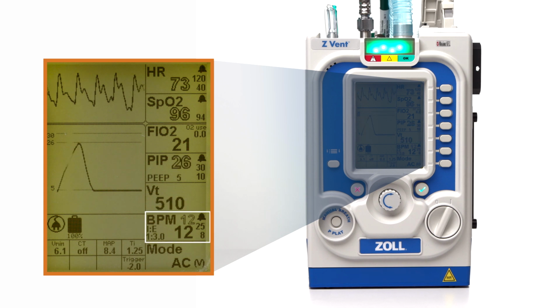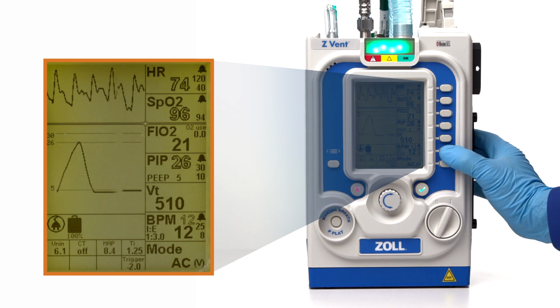The sixth window is breaths per minute, or BPM. In this window, the user can set the desired breaths per minute, the high breath rate and low breath rate alarms, and the I to E ratio, which is the ratio of how much of the breath is inspiration versus expiration. The BPM value can be changed from 1 to 80 breaths per minute.